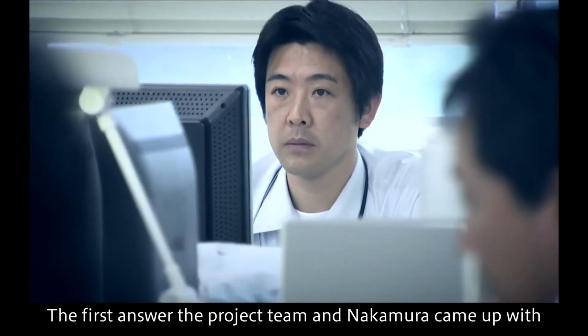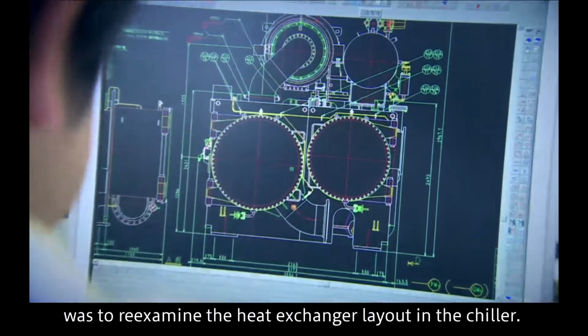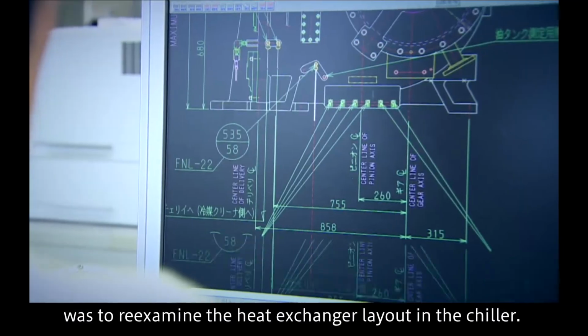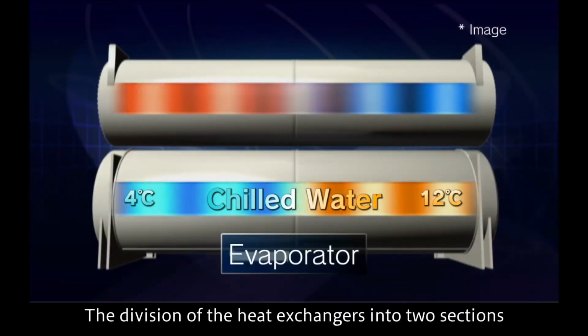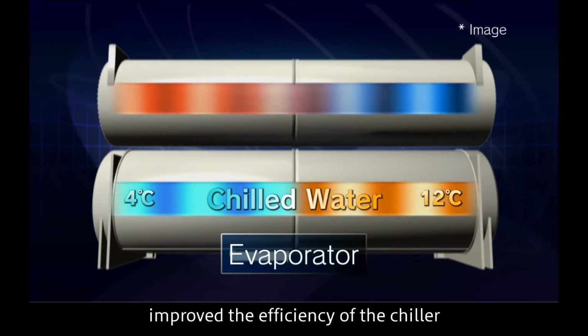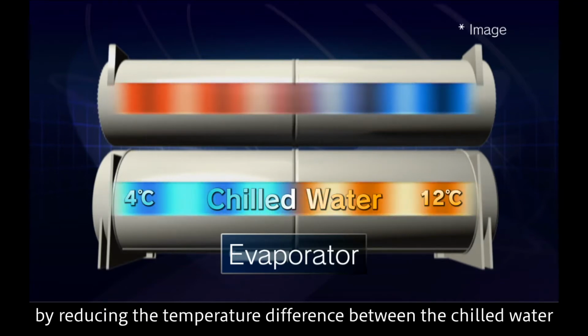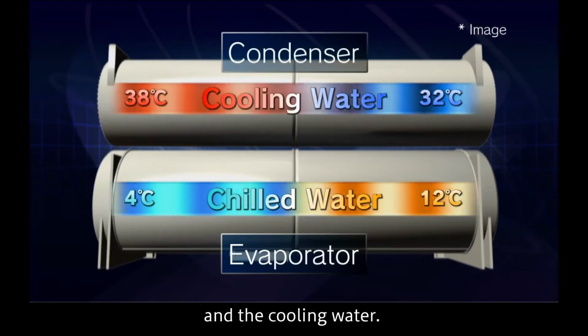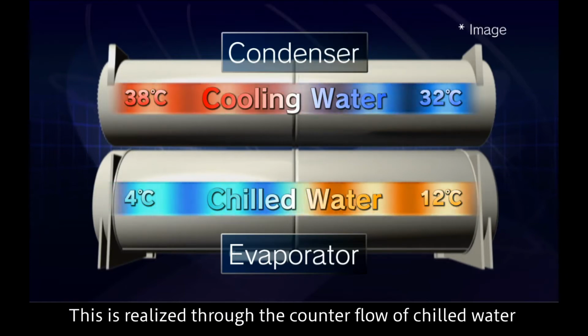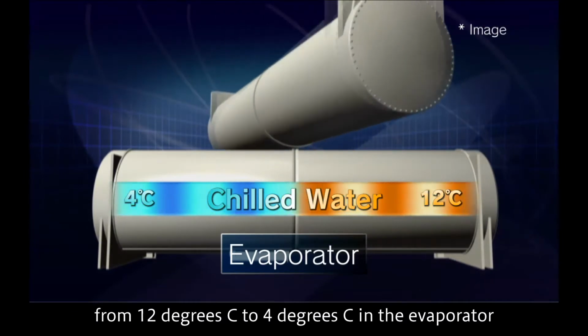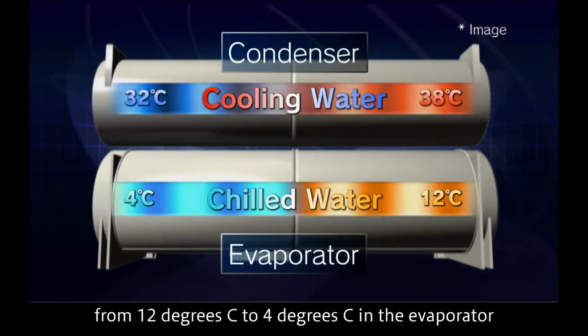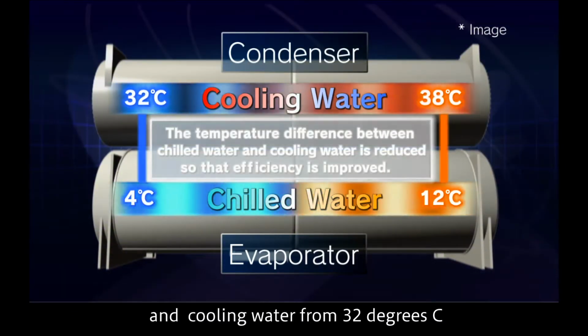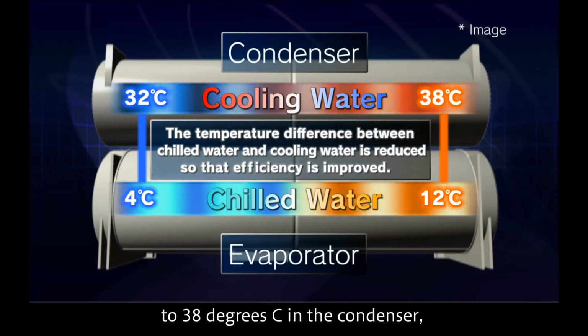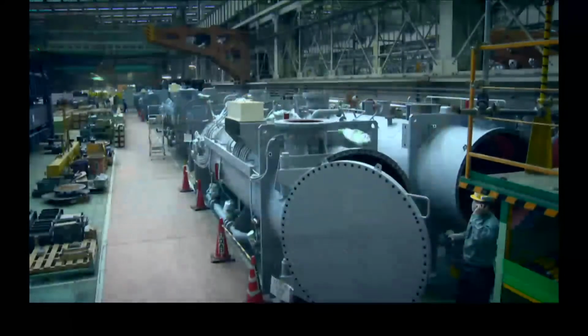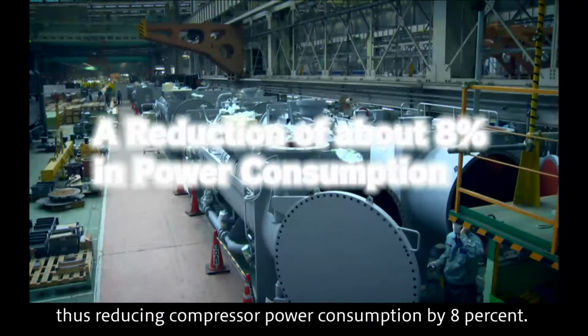The first answer the project team and Nakamura came up with was to re-examine the heat exchanger layout in the chiller. The division of the heat exchangers into two sections improved the efficiency of the chiller by reducing the temperature difference between the chilled water and the cooling water. This is realized through the counterflow of chilled water from 12 degrees Celsius to 4 degrees Celsius in the evaporator and cooling water from 32 degrees Celsius to 38 degrees Celsius in the condenser, thus reducing compressor power consumption by 8%.